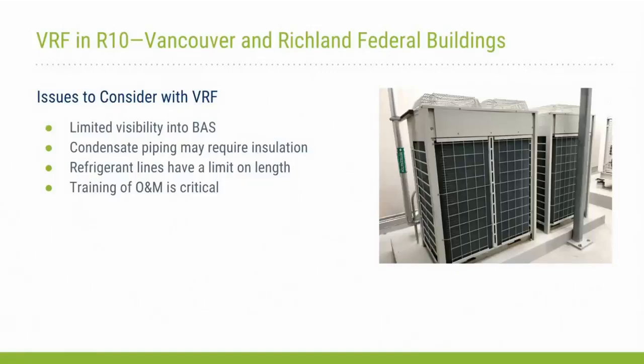Condensate with these systems, so they're either gravity or they're pumped from the unit itself, from the cassette. I've seen both. This installation was a pump installation, so you have alarms associated with the pump within the cassette unit, but then it's going to be pumped. In this installation, they pumped it to another booster pump, if you will, a condensate booster pump, which is not on the BMS.